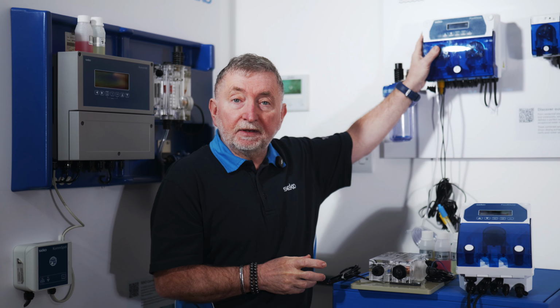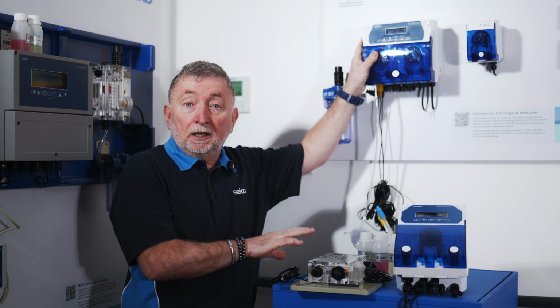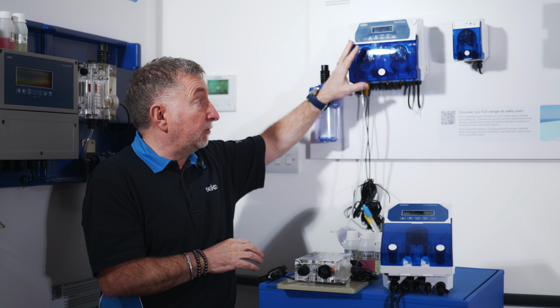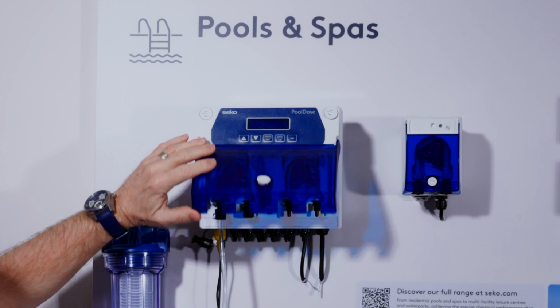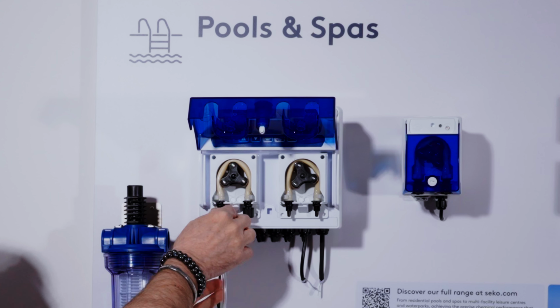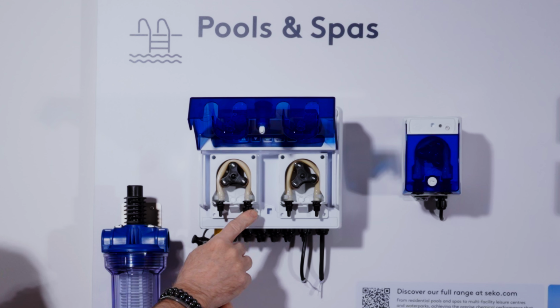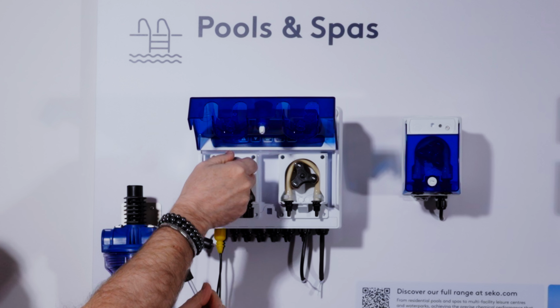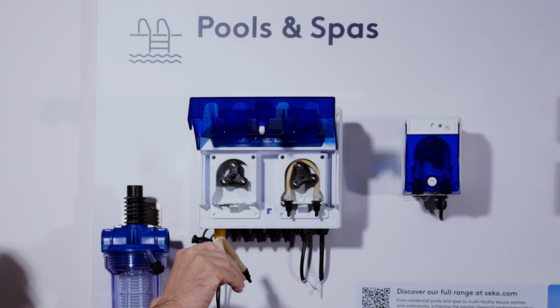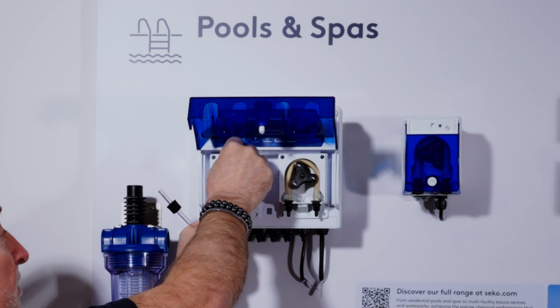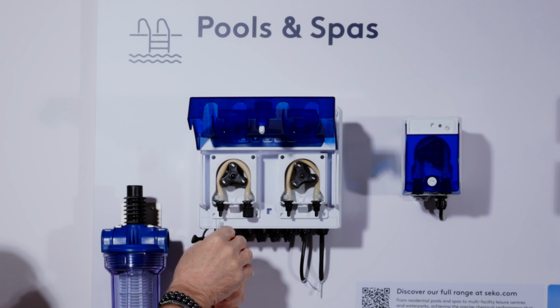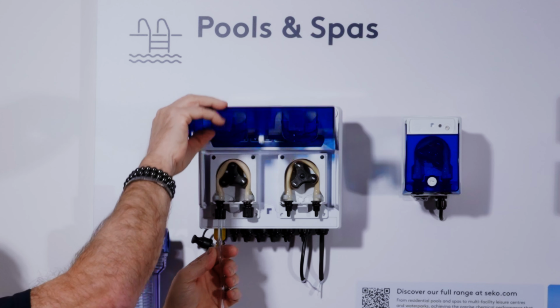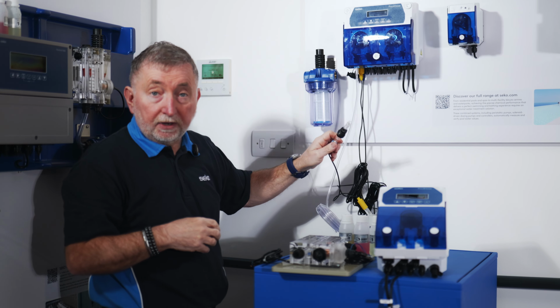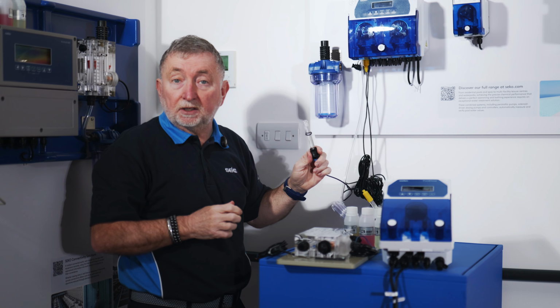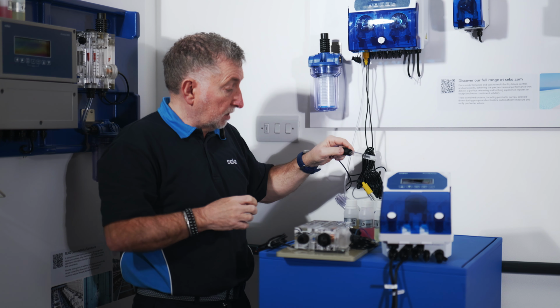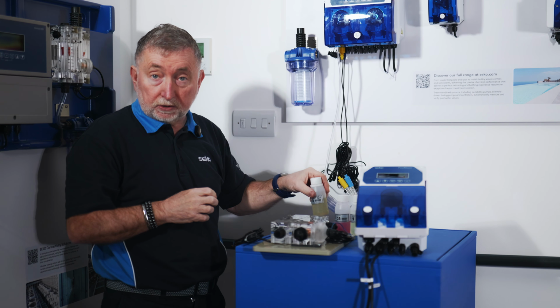These units are designed to be very user-friendly and low maintenance. The only periodic replacement you will have is the peristaltic tubes, which can simply be replaced by removing the suction and discharge tubes, unclipping the peristaltic tube, replacing using the clips, feeding around the rollers, and then reconnecting the dosing tubes. The probes will also need periodic replacement, but if looked after they should last well in excess of a year, which also applies to the buffer solutions.